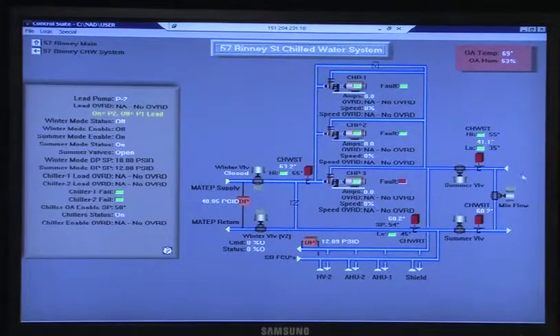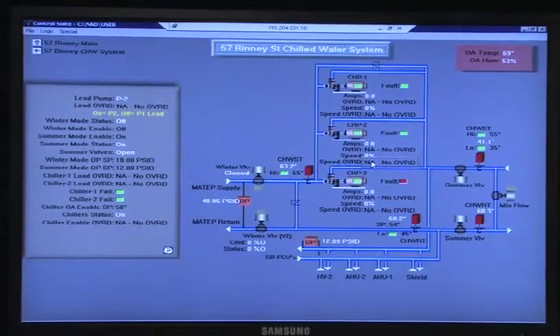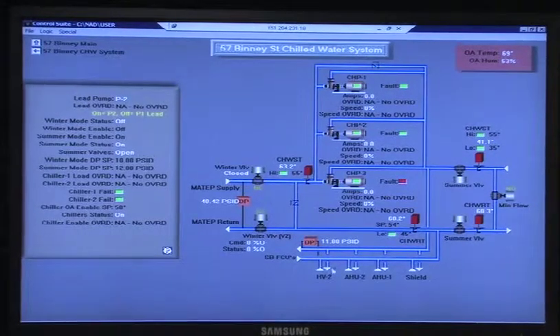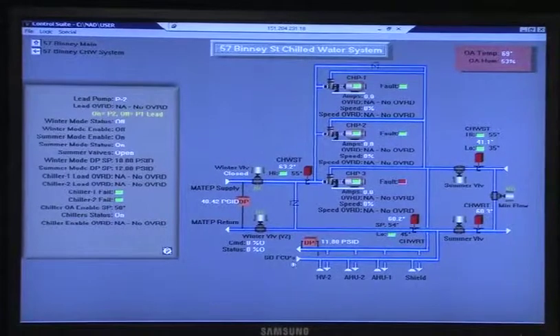Allowing chill water to flow through from our chiller plant to the pump sets, circulate through our building, down to all the units, shield cooling units, AHU1, AHU2, HVs, fan coil units, all this business, allow it to come back up, return, and head back to our chillers. These are MATEP, these are closed. These two valves stay closed. So MATEP water is isolated right here.